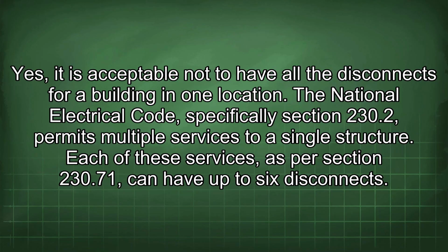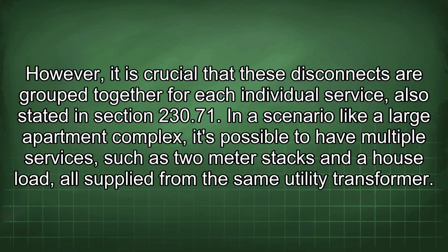Yes, it is acceptable not to have all the disconnects for a building in one location. The National Electrical Code, specifically Section 230.2, permits multiple services to a single structure. Each of these services, as per Section 230.71, can have up to 6 disconnects. However, it is crucial that these disconnects are grouped together for each individual service, also stated in Section 230.71.